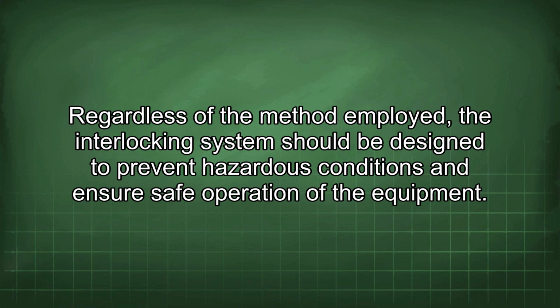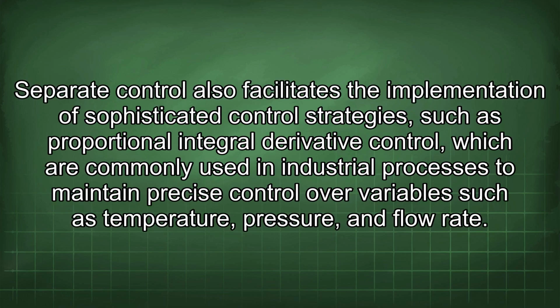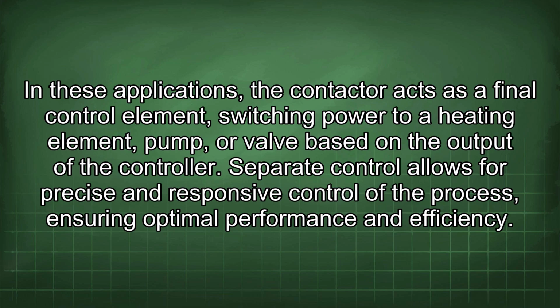operation of the equipment. Separate control also facilitates the implementation of sophisticated control strategies such as proportional integral derivative control, which are commonly used in industrial processes to maintain precise control over variables such as temperature, pressure, and flow rate. In these applications, the contactor acts as a final control element, switching power to a heating element, pump, or valve based on the output of the controller. Separate control allows for precise and responsive control of the process, ensuring optimal performance and efficiency.